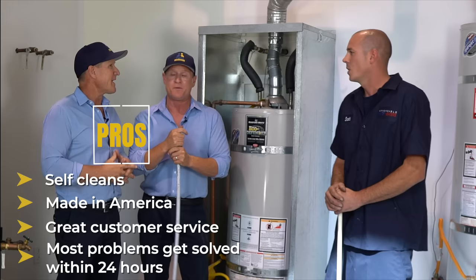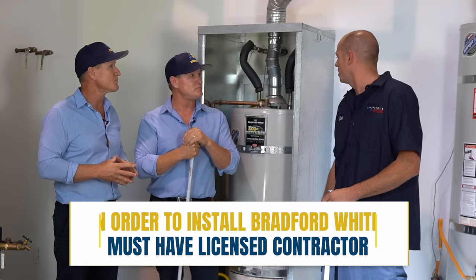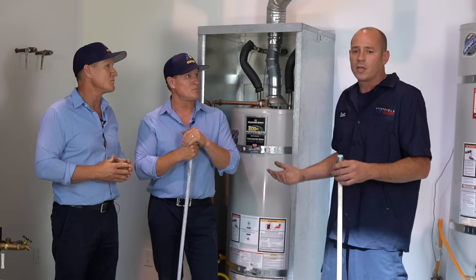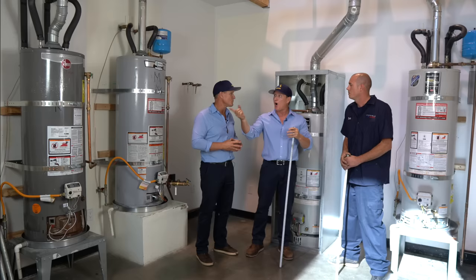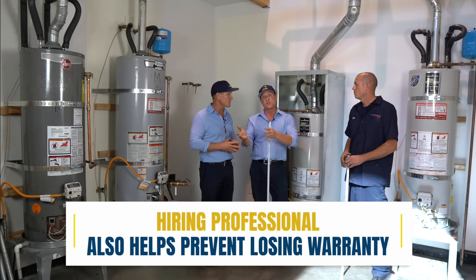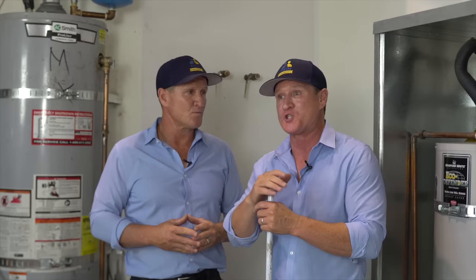The cost at a big box store versus Ferguson is pretty much about the same. The main difference is you do have to have a licensed plumbing contractor install Bradford White since you can't buy it at a big box store. Along with that, you'll need to pull a permit and bring everything up to code, so that's where extra cost might come in depending on your existing installation. Also, regarding warranty coverage on all heaters — if you don't have expansion tanks and if you're not having the pressure checked, that can void a warranty immediately. That's the key difference between hiring a professional versus doing it yourself.